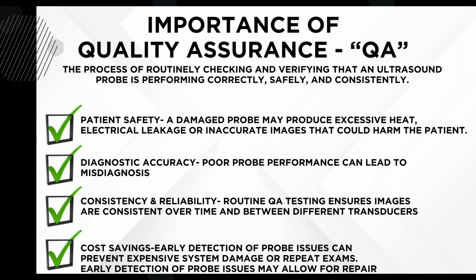So we're going to go through some of the tests that I typically do or my techs do for PMs on transducers. Typically when you go in and do a PM, there could be one transducer on the system, there could be 8 transducers on the system. We have a PM form that breaks down all of these tests, and we indicate our distance measurements for each transducer.